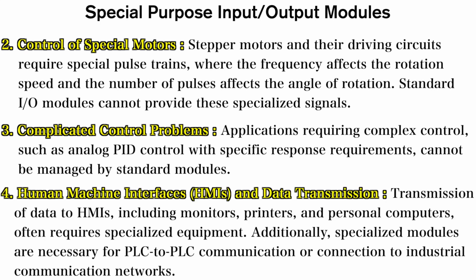Next are human machine interfaces, HMIs, and data transmission. The transmission of data to a human machine interface, which generally includes monitors, printers and personal computers, often requires specialized equipment. Additionally, these specialized modules are necessary for PLC to PLC communication or for connection to industrial communication networks. For this and similar cases, the special input output modules are designed. These modules typically feature their own microprocessor, which operates independently to perform the required task while it simultaneously connects to the main programmable logic controller processing unit for the transfer of data and control signals.